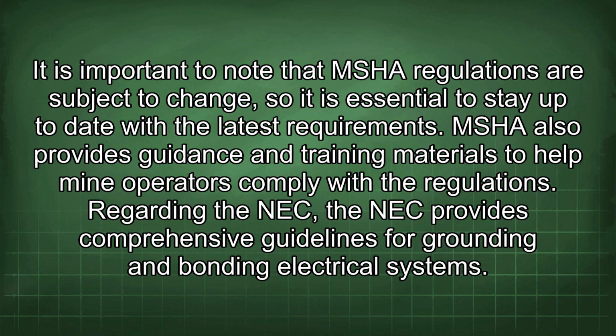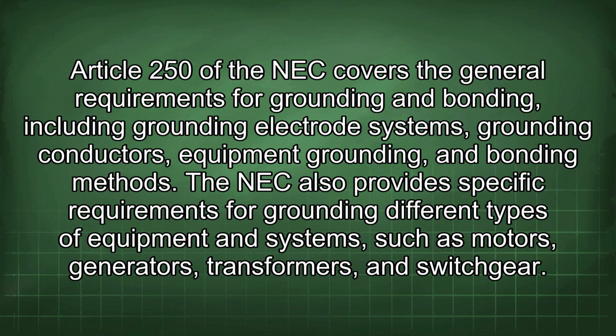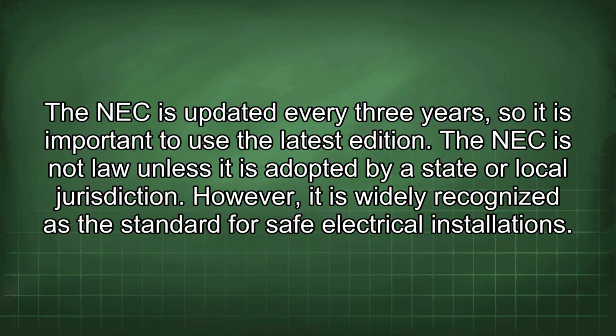Regarding the NEC, it provides comprehensive guidelines for grounding and bonding electrical systems. Article 250 of the NEC covers the general requirements for grounding and bonding, including grounding electrode systems, grounding conductors, equipment grounding, and bonding methods. The NEC also provides specific requirements for grounding different types of equipment and systems such as motors, generators, transformers, and switchgear. The NEC is updated every 3 years, so it is important to use the latest edition. The NEC is not law unless it is adopted by a state or local jurisdiction. However, it is widely recognized as the standard for safe electrical installations.